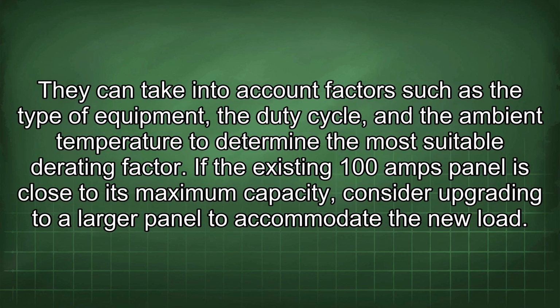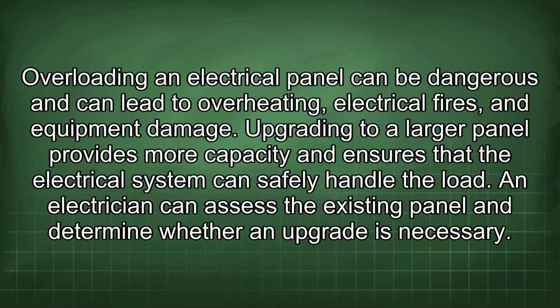They can take into account factors such as the type of equipment, the duty cycle, and the ambient temperature to determine the most suitable derating factor. If the existing 100 amp panel is close to its maximum capacity, consider upgrading to a larger panel to accommodate the new load. Overloading an electrical panel can be dangerous and can lead to overheating, electrical fires, and equipment damage. Upgrading to a larger panel provides more capacity and ensures that the electrical system can safely handle the load. An electrician can assess the existing panel and determine whether an upgrade is necessary.